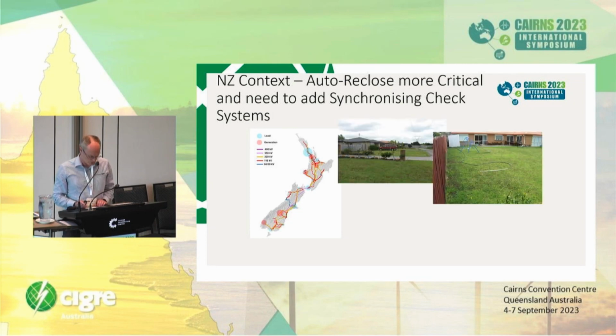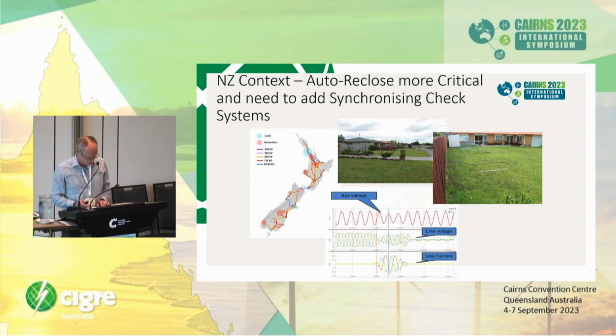After power system faults, Transpower generally require a time-consuming line patrol to check for causes such as dangerous joint failures before manually closing the circuit back in. Auto-reclose of transmission circuits has become more important to promptly maintain supply. Depending on grid configuration, the grid and embedded generation may become separated following a fault. Reclosing onto generation may cause high currents and damage unless measures are taken, such as applying synchronism check and anti-islanding before auto-reclose.